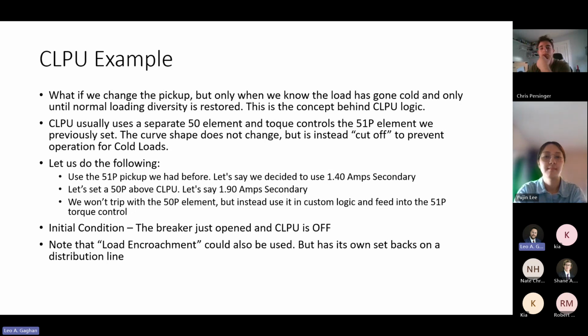So let's do the following. We'll use the 51P pickup we had before. Let's say we decided upon 1.4 amps. But now we have to set the cold load above a value of, let's say, 1.9. We're going to set this 50P element, but instead of tripping with it, we're going to use it in some custom logic and drive that 51P torque equation. So we're going to look at some logic. It can be a little tricky to follow, but we're going to start with an initial condition of the breaker just opened and the cold load pickup function is off.